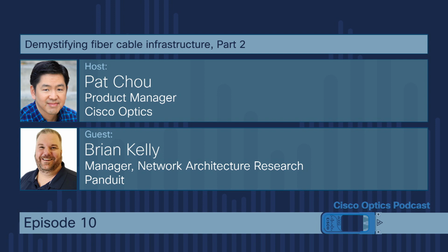Sorry, on the longer runs, you said you might only be able to do transceiver plus fiber, because if it's over like 50 meters, it's just going to be too difficult to run an AOC, and a DAC wouldn't work because of the bulky termination. Yeah, the bulkiness of it, and also the fact that you can't really have structured cable in place with either one of those, AOCs or DACs. Right, because when you upgrade to a new data rate, you'd have to replace the whole thing.